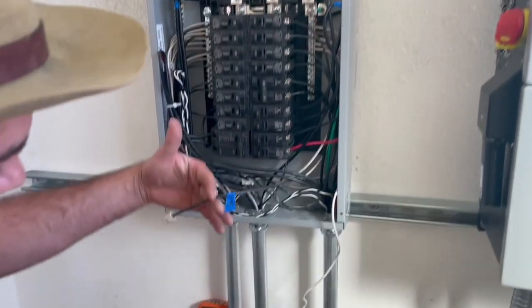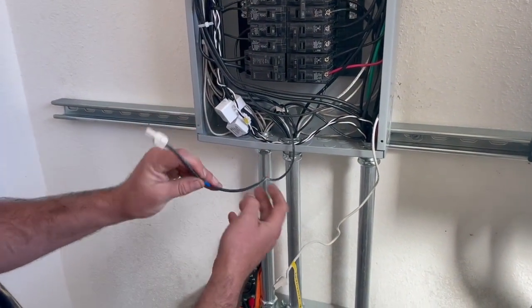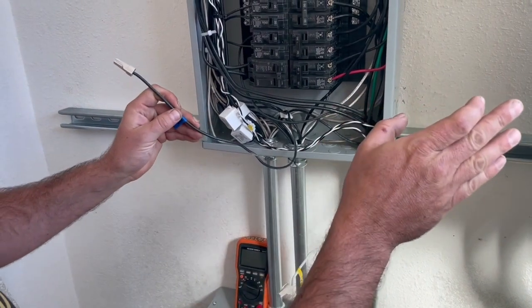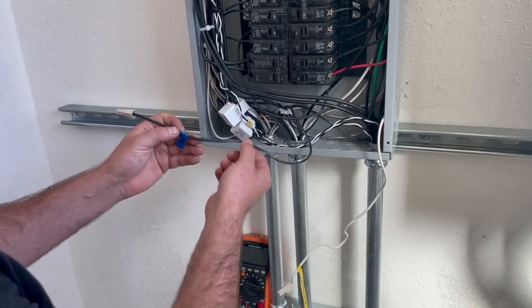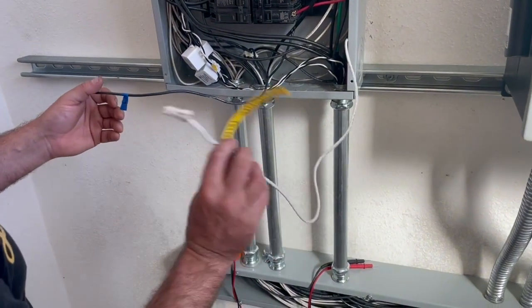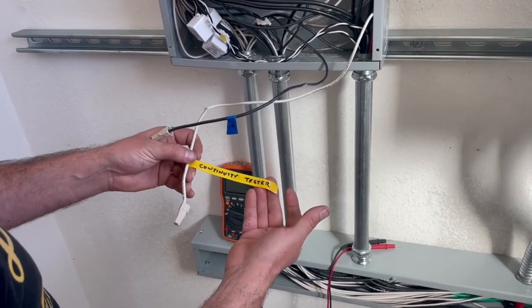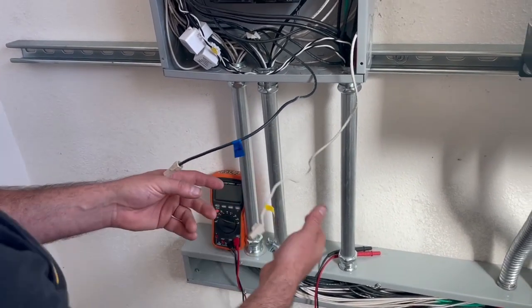You notice these two wires hanging here. This one labeled here never made it to that side. It got pulled too far. So this is a derelict wire we have to manage. This extra white here, we have both ends sticking out of the panels. We're gonna leave it in here for a continuity tester for future reference if we need to.